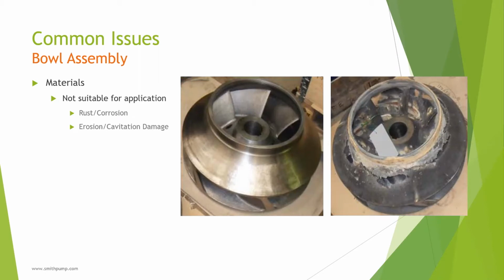If cavitation is expected due to insufficient NPSHA, an upgrade to nickel aluminum bronze could help the impellers last much longer than the standard bronze. Nickel aluminum bronze is a good choice for withstanding cavitation and erosion, but if in doubt, just ask the pump supplier for their suggestion.